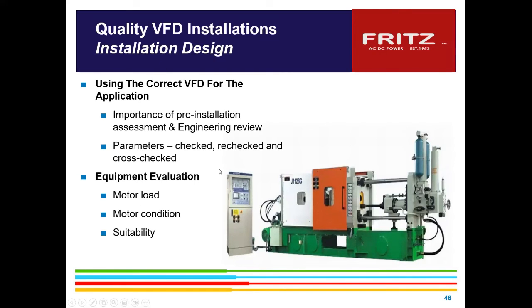This happened to be what I was talking about on the injection molding machines that I've done a lot of retrofits on. We put the controls on, and instead of the hydraulic pump running full speed all the time, the system would actually pick up circuits inside where the process was and speed up and slow down the motor. One project I did in Massachusetts was an optical lens company. They had very long cure times, so the motor was sitting there running on a 4-minute cycle. In that cycle, they were really only truly using the clamp and the other part about 20% of the process. So it had a big return on investment, a lot of speed savings, plus it reduced the hydraulic cooling requirement that they were putting up to chillers on the roof. It actually saved a lot of money operating the units.